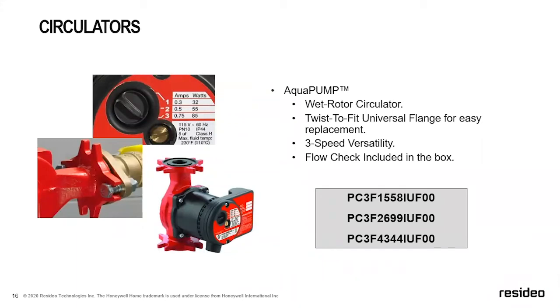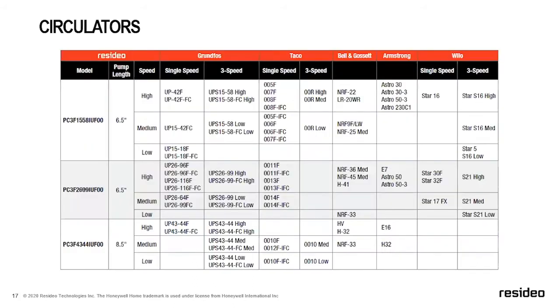And the other thing I'd like to highlight, the flow check comes in the box, okay? So if you want to install it, you can. If you have an external flow check or don't want to have a check valve, you don't have to install it. In the manuals, we do give you an example of what the pump curves look like with and without the flow check. So truly universal. And to further that point, if you look at this cross-reference, there are 3 different size pumps, and you can see all the manufacturers, the competitive ones that we are going to replace with that single unit. And again, 5-year warranty.